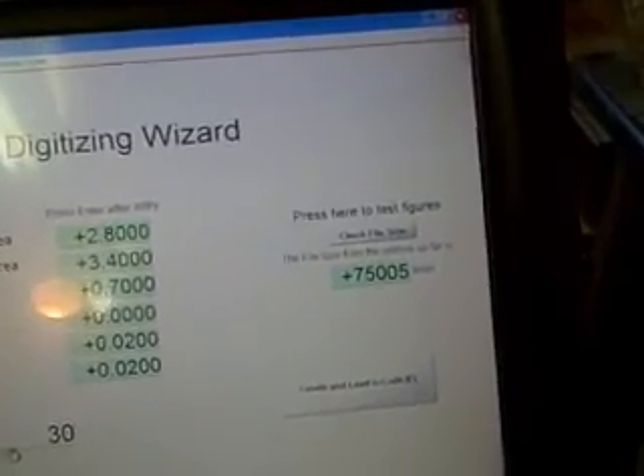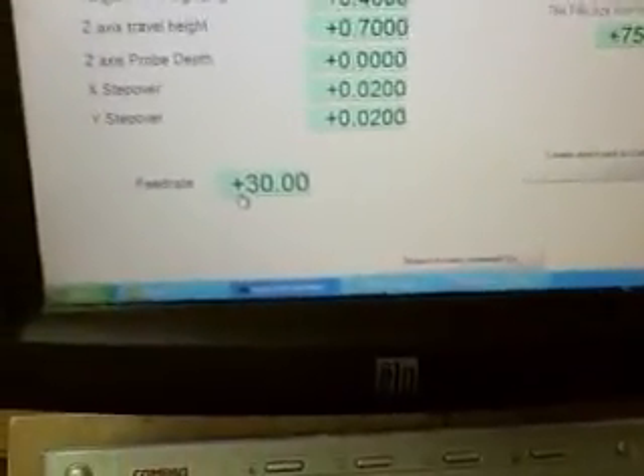Our feed rate we're going to set to about 30 inches a minute. I wouldn't recommend you do anything over 30 until you know your probe and know what you're doing, and have done this several times and are comfortable that your probe will stop in time.